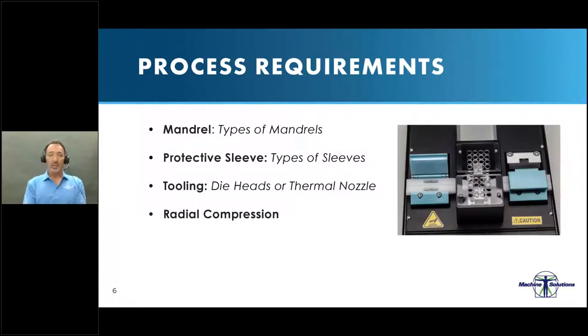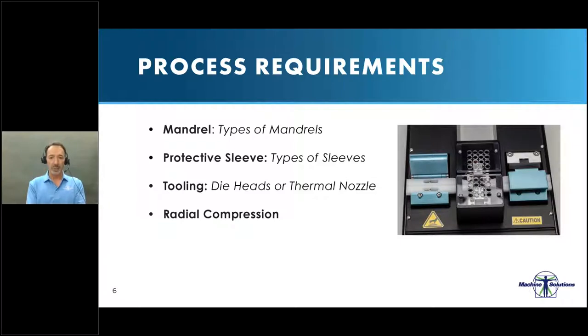Let's talk about the materials you need to create bonds. Number one are mandrels, typically stainless steel and preferably with PTFE or some other lubricious coating. It is almost impossible to create an overlap joint without supporting the ID of the materials — if you're getting the polymer hot enough to flow, you're getting it hot enough to collapse the ID. Therefore, some type of support must be given to prevent tube closure. Protective sleeves — typically FEP, often polyester, sometimes polyolefin — serve a number of functions: they protect materials from sticking to die heads, add radial compression, and facilitate smooth blending of the polymers.